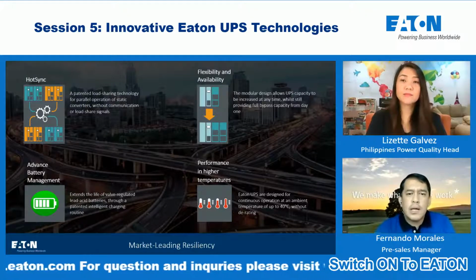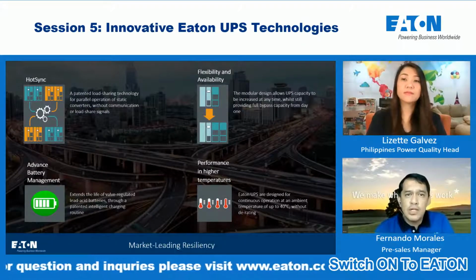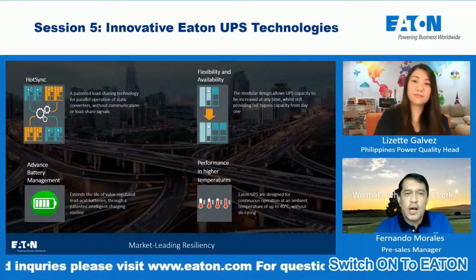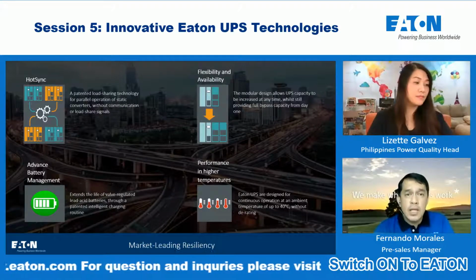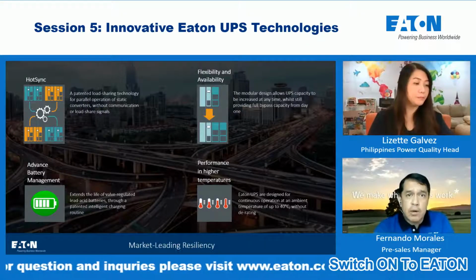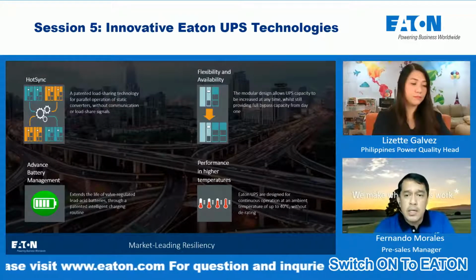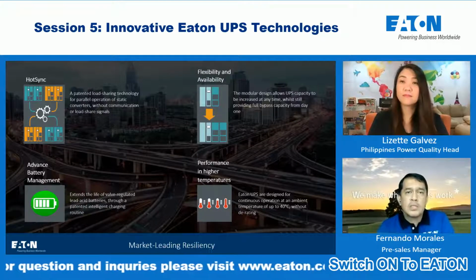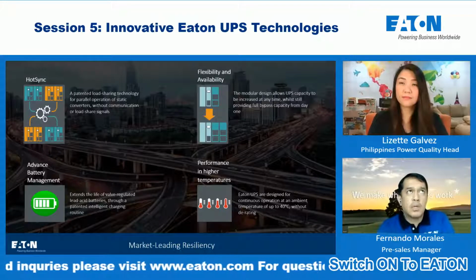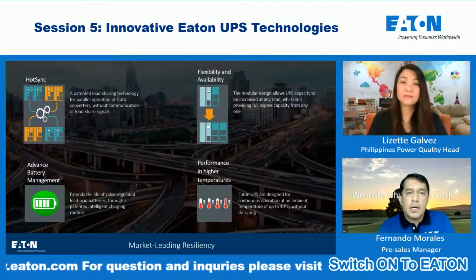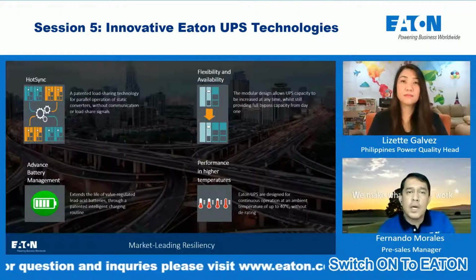So first, let's identify the reasons why we parallel a UPS, or why we parallel power modules in a UPS. The first reason is we want to increase the capacity of our UPS, maybe because the load increases already and the capacity of the UPS cannot deliver the power demanded by these loads. For example, if we have 100 kVA on day one, and then suddenly the customer load increases to around 125 or 150 kVA, we can parallel another 100 kVA and come up with a 200 kVA UPS capacity. So that's one of the reasons why we parallel a UPS.